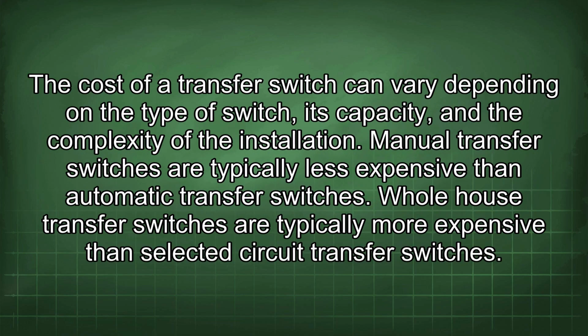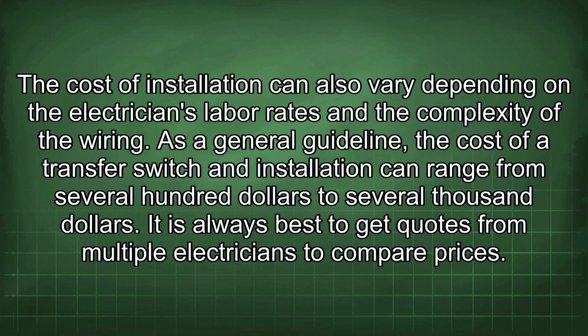The cost of a transfer switch can vary depending on the type of switch, its capacity, and the complexity of the installation. Manual transfer switches are typically less expensive than automatic transfer switches. Whole house transfer switches are typically more expensive than selected circuit transfer switches. The cost of installation can also vary depending on the electrician's labor rates and the complexity of the wiring. As a general guideline, the cost of a transfer switch and installation can range from several $100s to several $1,000s. It is always best to get quotes from multiple electricians to compare prices.